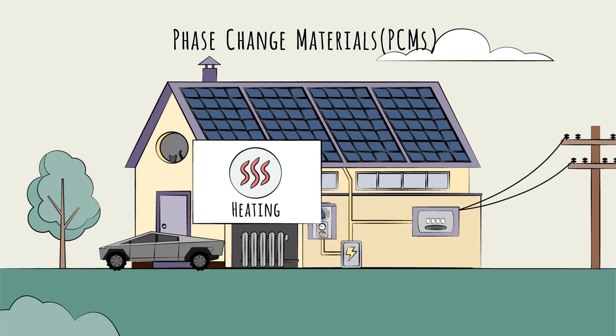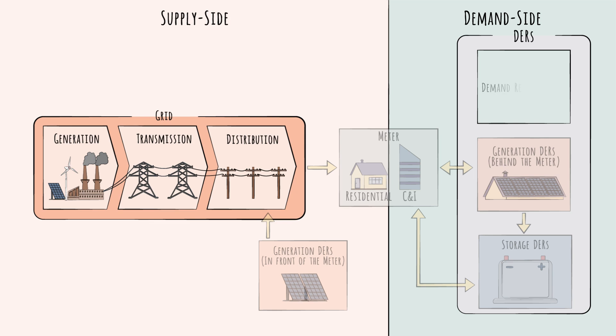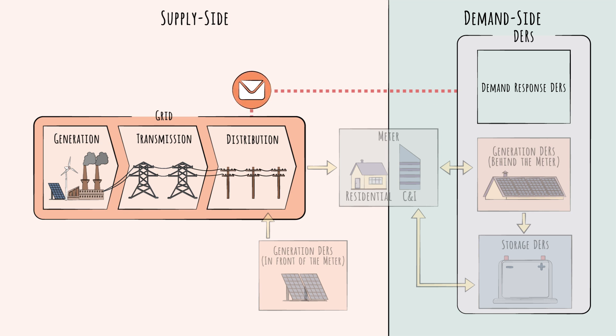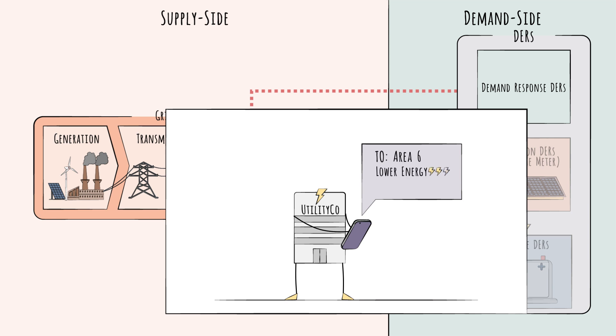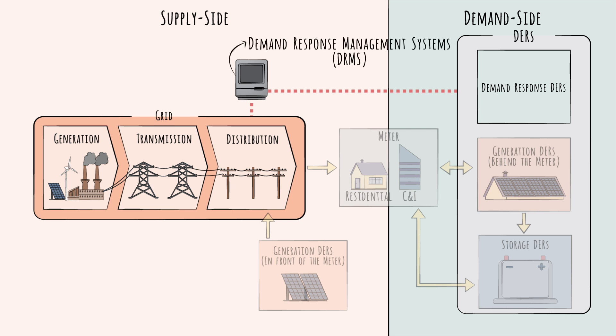To summarize: generation DERs work by adding supply, and storage DERs work by putting energy into on-site inventory. The final set of DERs work by reducing or deferring the demand for power – these are the demand-response management resources. The word 'response' refers to the fact that these reductions or deferments are often triggered by signals from the supply side, usually from the utility. These signals are called demand-response events. Historically, we've only made use of limited, centralized demand-response tools, such as utilities sending messages to customers asking them to use less power – commonly called a behavioral demand-response event, or BDR. The systems that help send demand-response events are called demand-response management systems, or DRMS.